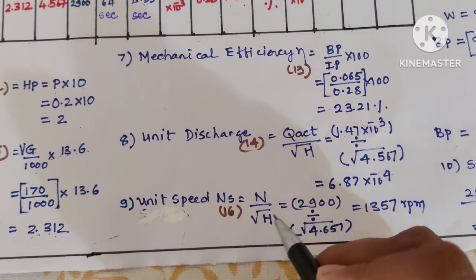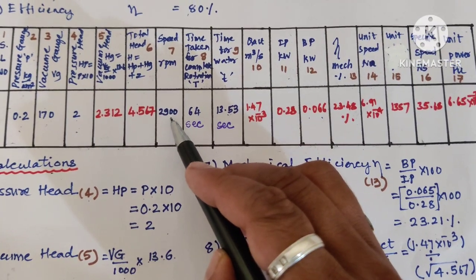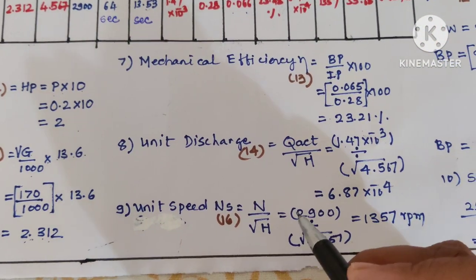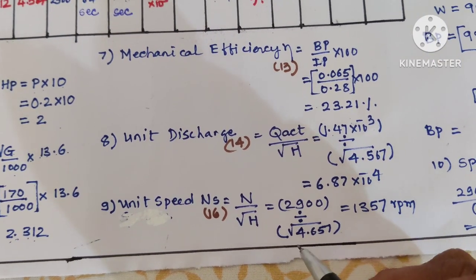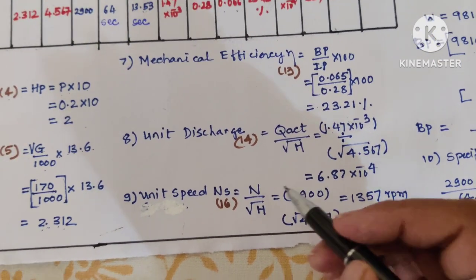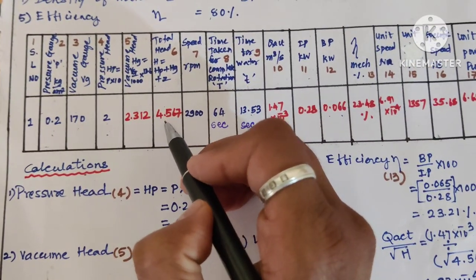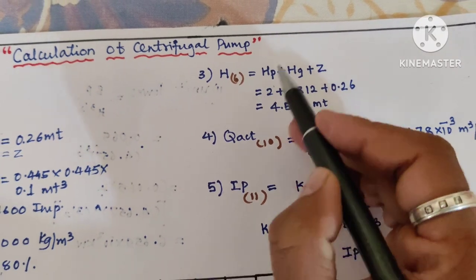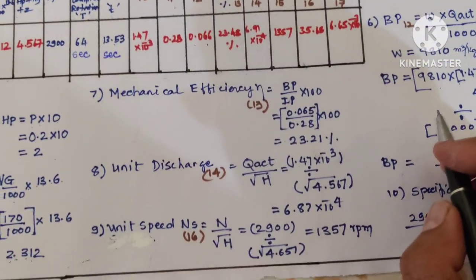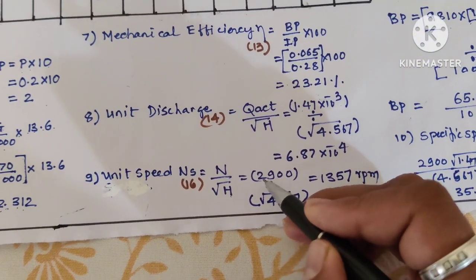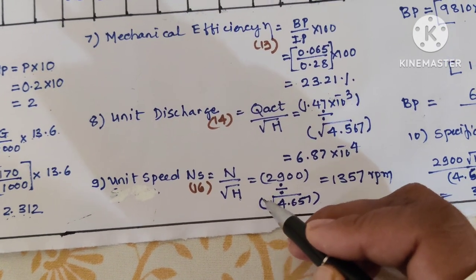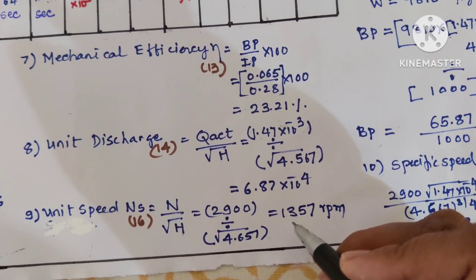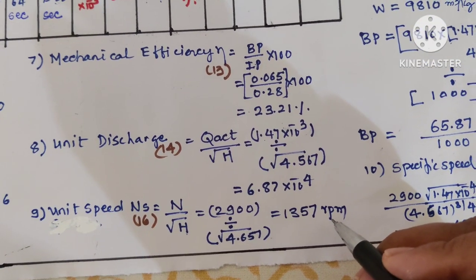Next is unit speed: N / √H. N from tachometer is 2900, so 2900 / √4.657. Total H is the addition of all head values. Substituting 2900 / √4.657, we get 1357 rpm.